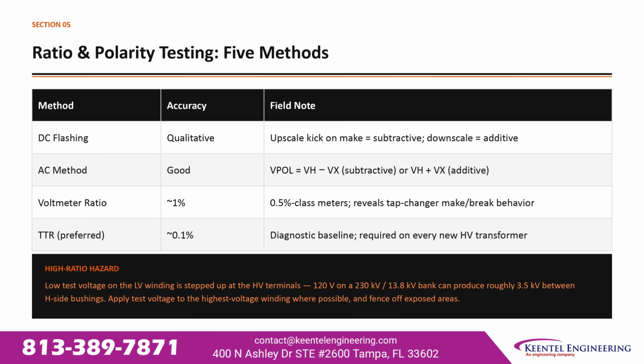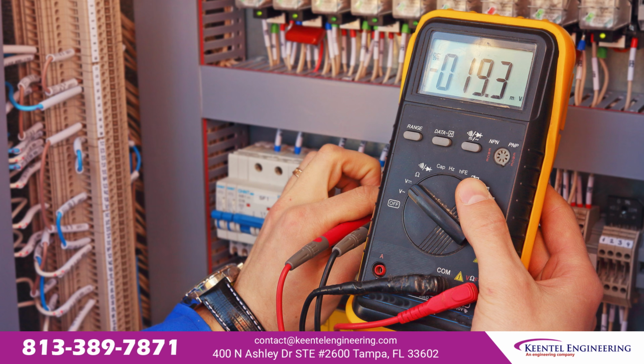5 methods exist for ratio and polarity testing. DC flashing is qualitative. An upscale kick on make signals subtractive polarity, downscale signals additive. The AC method is good, using the relationship between the high and low voltage windings. Voltmeter ratio testing reaches about 1% accuracy using 0.5% class meters and reveals tap changer make and break behavior. TTR is the preferred method, reaching about 0.1% accuracy, and it's required as the diagnostic baseline on every new HV transformer. One hazard worth flagging: low test voltage on the LV winding gets stepped up at the HV terminals. As little as 120 volts on a 230 kilovolts to 13.8 kilovolts bank can produce roughly 3.5 kilovolts between H-side bushings. Apply test voltage to the highest voltage winding where possible and fence off exposed areas.